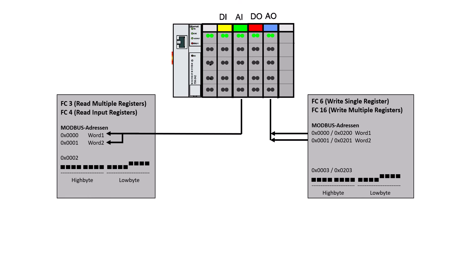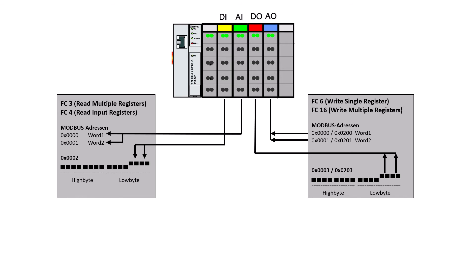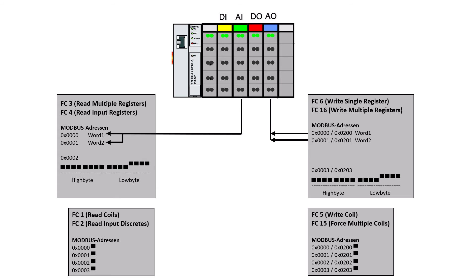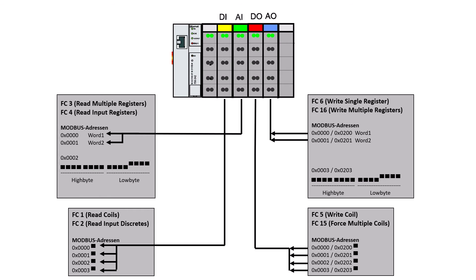If digital signals as well as analog signals are read or written via register functions, the address area of the digital signals follows the analog signals. If further analog modules were to be added, the address range of the digital signals would be shifted. In order to avoid this, the digital signals are given the coil functions and we have them in a separate address range.